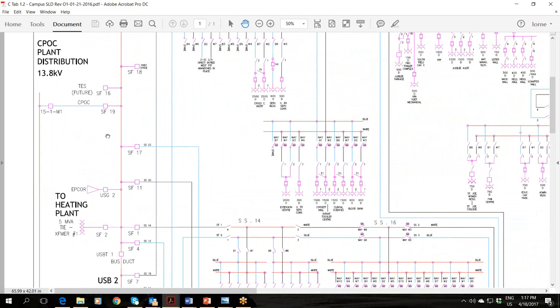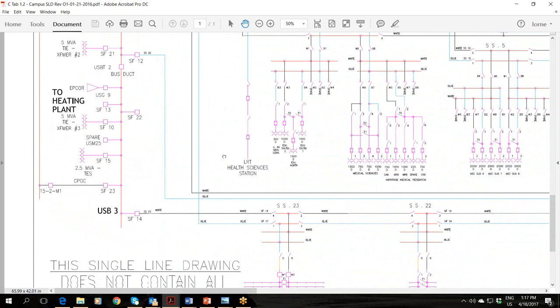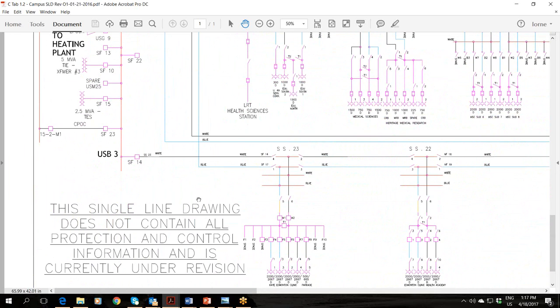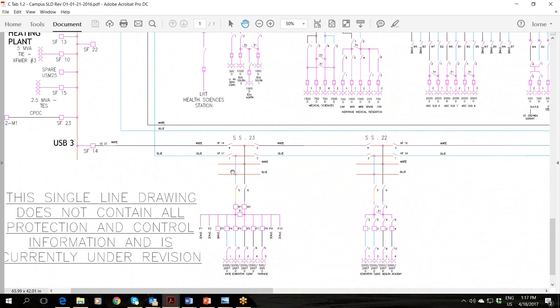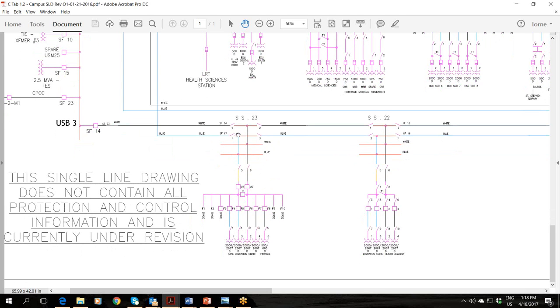This blue supply here, if you follow it way up, comes off of bus 1 associated with the south switching station. And if you remember, bus 1 was a totally different transformer, totally different supply all the way up at the EPCOR Garneau substation level. So we truly do have 2 supplies coming into this grouping of sectionalizers. Something you'll see a little later from the pictures, these 3 switches that are the blue supply are actually a different physical lineup of equipment than the white supply. Same room, but 2 different pieces of equipment. So they are separated. From these sectionalizing stations, they do go down into the building, and we'll talk about that a little more in a couple minutes.